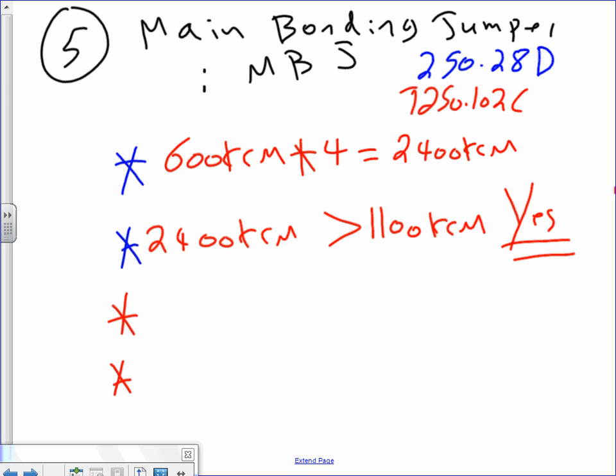So the 600 KCM is the phase size, right? You multiply it by 4 because we have 4 of them. Yes, sir. Where did 1100 come from? The 1100. If you guys go to table 250.102C, right underneath it, it will tell you, hey, if you exceed what the table is giving you... Can you see that? If you run out of wires, can you guys see note number 1 underneath it? Note number 1 underneath it. If it's larger than 1100 KCM, only if it is, do the following.